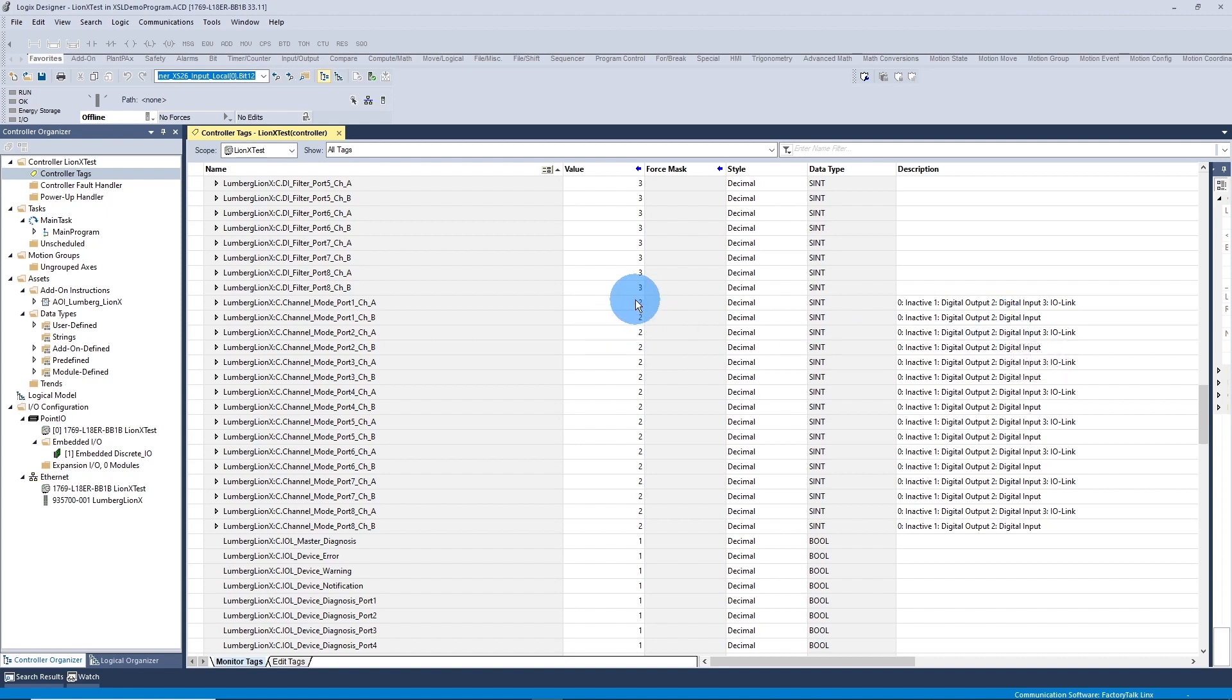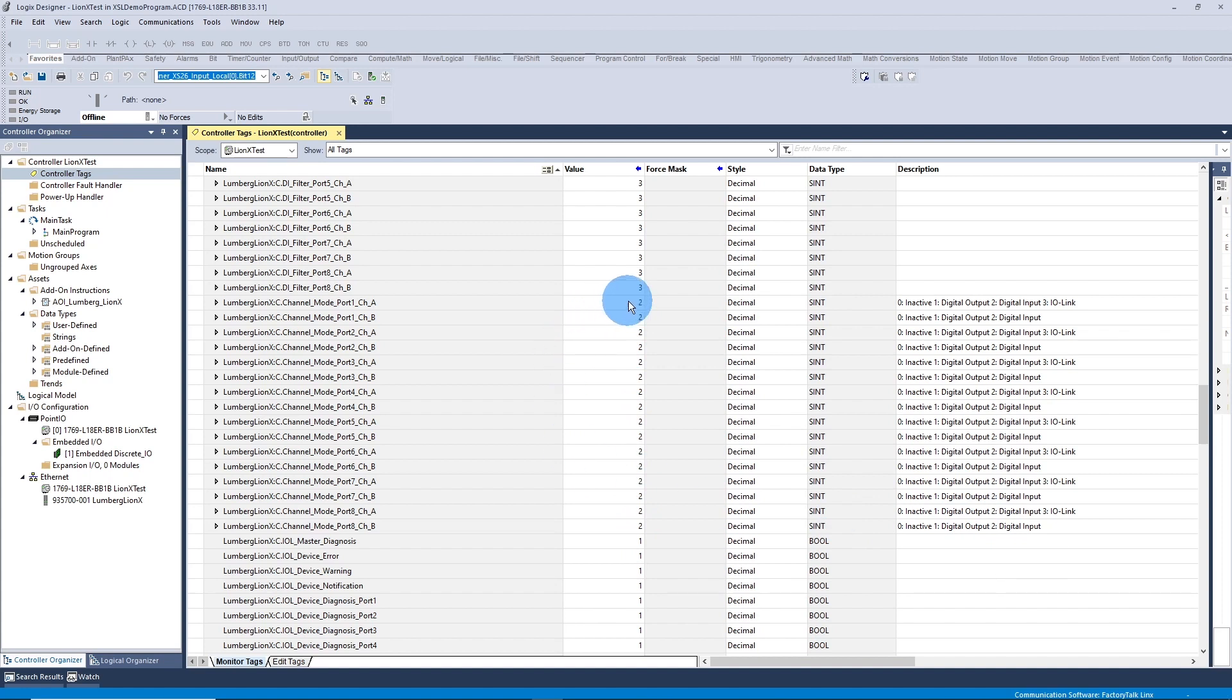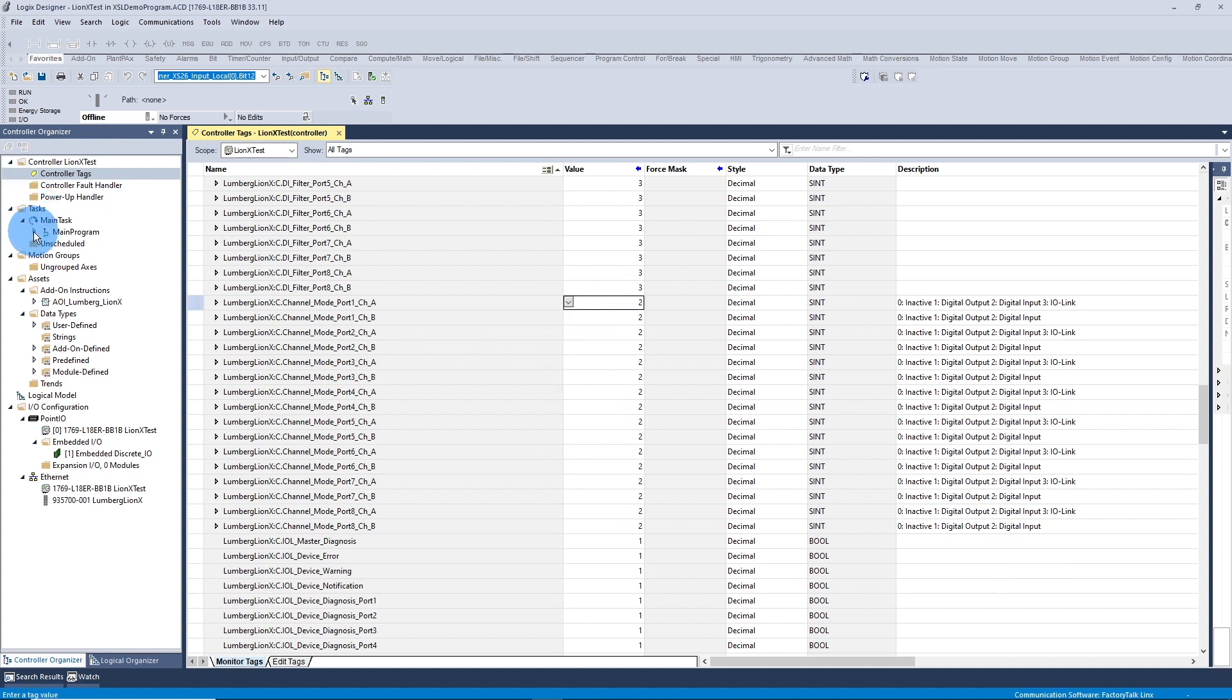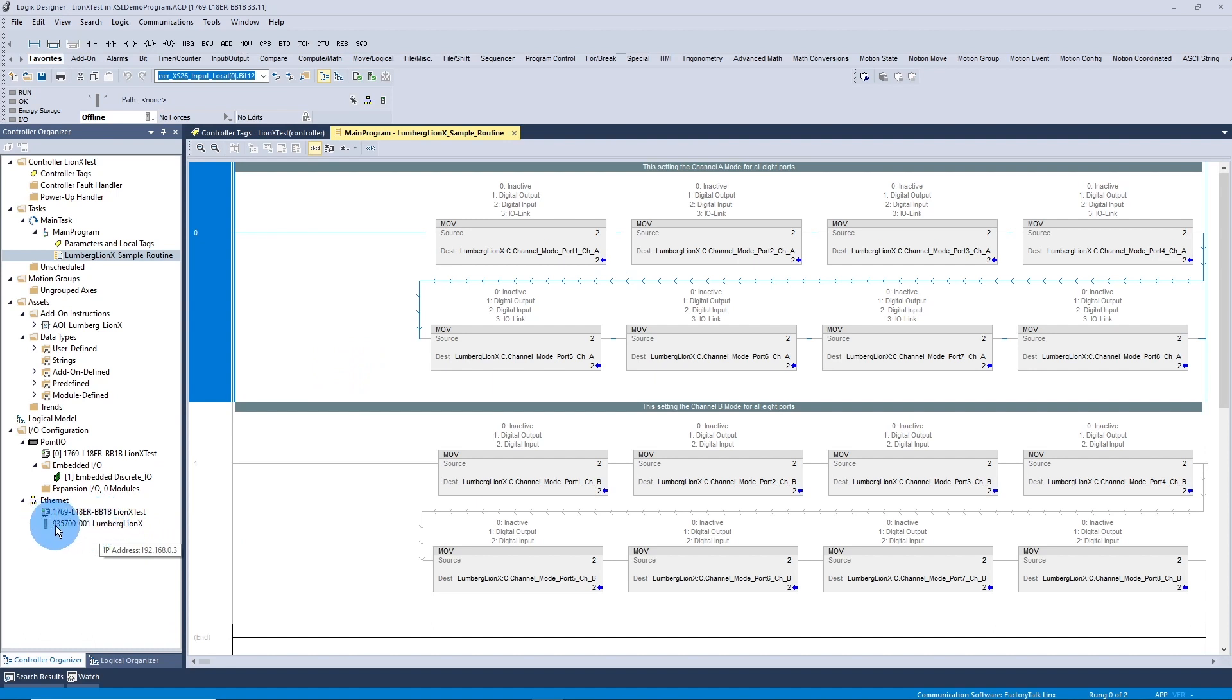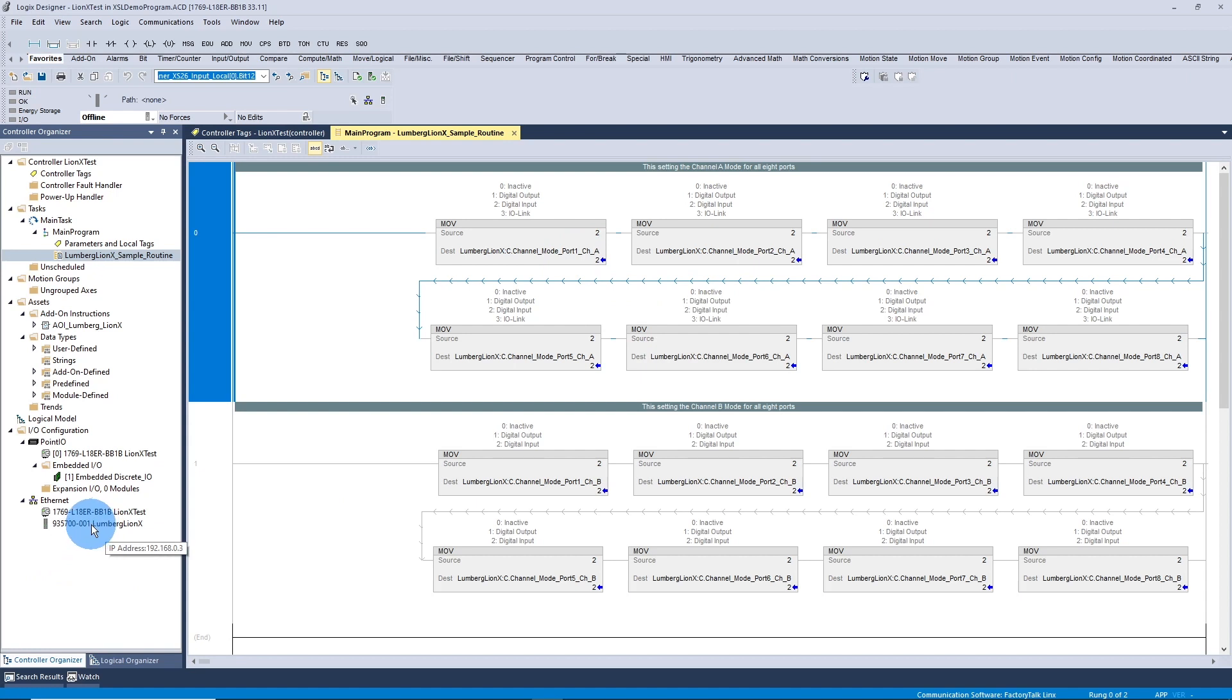In my case, I'm setting a 2 to every port to make everything a digital input. So you can change them here, or I have a little sample routine where I'm moving a 2 to each port. If you do this while you're live, you'll need to power cycle the block after you've made these config changes, or inhibit the module and then un-inhibit the module. And that'll take effect.